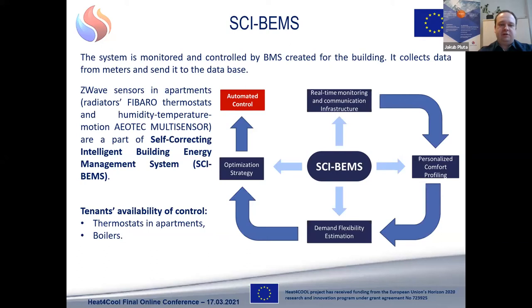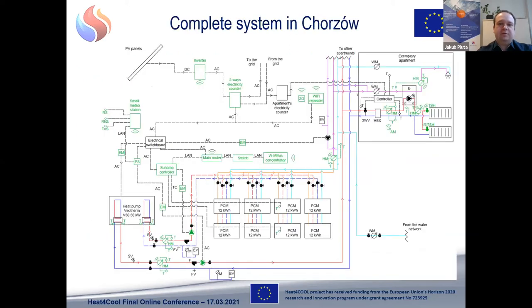They can change the thermostat set points in radiators and also the set points in boilers. The changed set points in the radiator thermostats will be remembered by the system as requirements of the tenants, and then the system will adjust to these new set points.